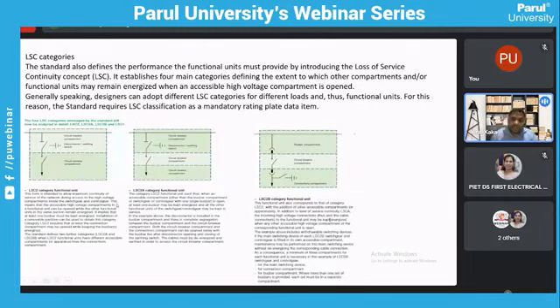So that ensures the technician as well as operator safety in this case. This is just a type of classification or the categories in which our switchgears have been defined. Normally, medium voltage switchgears will fall under the LSC2 functional category, where your cable compartment, circuit breaker compartment, and the bus bar compartment will be totally isolated from each other. And that ensures that any activity can be done, even while the bus bar is live, and that ensures a bit of technician safety. As we can see, in the LSC2 category functional unit, it's only a breaker compartment and a cable compartment in one section, and then switch disconnector in one. So in an LSC2A, you are seeing that the circuit breaker compartment and the disconnector compartment are slightly reversed in that case.